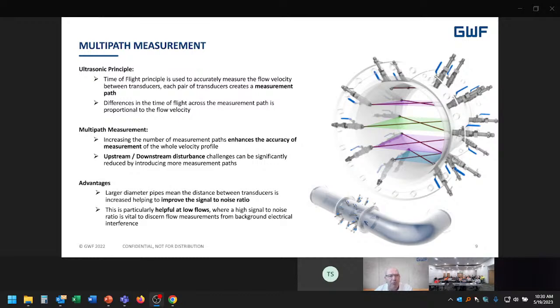The fact that we can put multiple paths in here, although that looks like a bit of a school science project with lots of pipes coming out of it, means that in this type of application we can measure to less than 1%, maybe 0.5% accuracy on a very large pipe. So you can be sure, if you're looking at custody transfer, or wastewater measurement from a large commercial client or other applications, that we can measure it very accurately, or we can reduce some of the paths if the high accuracy is not completely required.